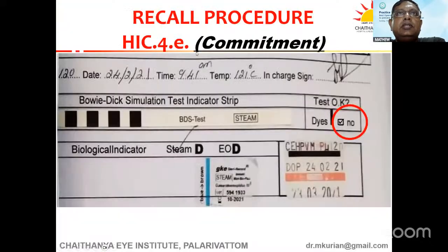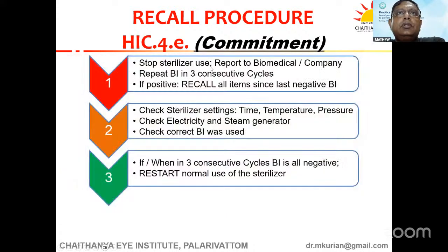Now, what happens if the dry cycle is incomplete? This kind of a thing is not acceptable, and this is called as a recall procedure, which is HIC 4E. And is the test okay? It should be documented as not okay. And in such a kind of situation, we should stop the sterilizer use, report to the company, repeat the biological indicator in 3 cycles. And if any of these are positive, then we should recall all the items since the last negative biological indicator. We should check the sterilizer settings, check everything is correct. And then if we get 3 consecutive biological indicator cycles as negative, then we can start the use of the sterilizer.